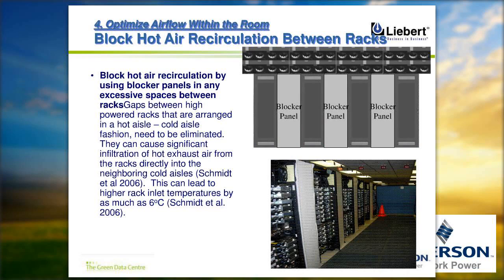In India, we observe that average data center density is about 4 to 5 kilowatt, which means maybe sometimes only one third of the rack is occupied and the balance racks are empty. But most often those racks are not blanked off. So there is a high potential of mixing of air from cold and hot together, or just cold air passing through a rack and getting mixed in the hot aisle. So it is important to use blocker panels when the rack is completely empty, or to use blocking plates when there are air gaps in between the servers.